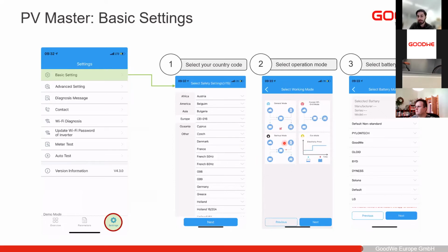The backup mode here is in case you have very frequent backups or grid faults and you need to have the backup set up in a specific way. But even in general mode, you will have the backup. For eco mode, this is a time of use type of mode, and here you can set up specific times when you want to charge or discharge the battery. So if you want to charge it in the morning and discharge it in the evening, you can set up specific time slots here, and any time you don't configure will automatically be run in general mode.